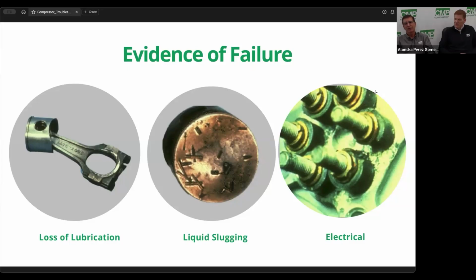And I've never really known of a compressor failure that was caused by too much Acid Away or additives in the oil like that. But that's a personal opinion, whether you want to use Acid Away or a suction line filter. But if you decide to put a suction line filter on it, try to mount it vertically and not horizontally so it doesn't trap any oil. Sometimes it doesn't take but a coffee cup full of oil to damage the compressor on a startup.